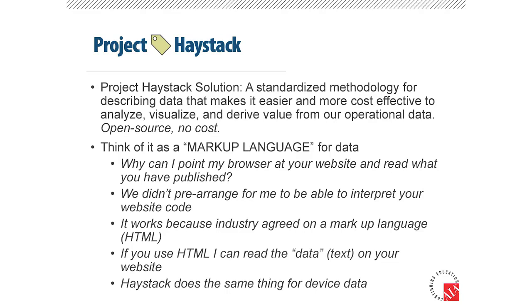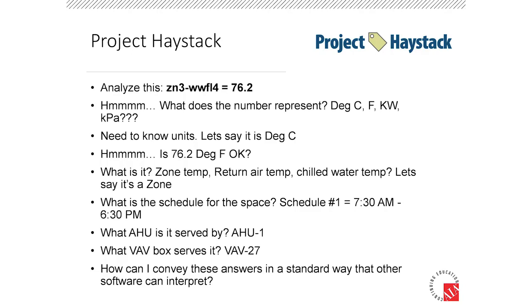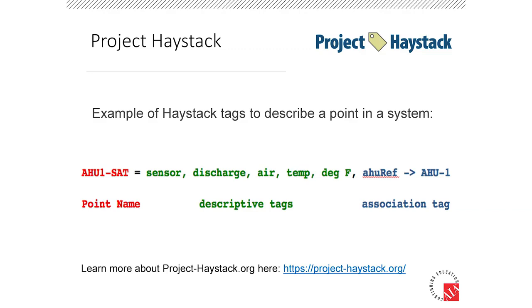We talked about an example of the problem, right? What does ZN3 WWFL4 mean? But here's how that would get marked up. Here's an example of a set of haystack tags to describe that point. In red, we've got the point name in the BAS system, and we know there's a huge problem with point names, there's no standard, everybody names the stuff differently, and you know what, we're never going to solve that problem, so don't try.